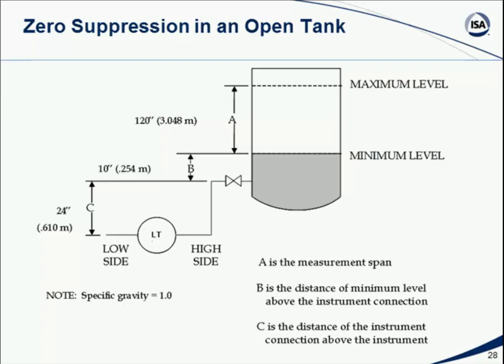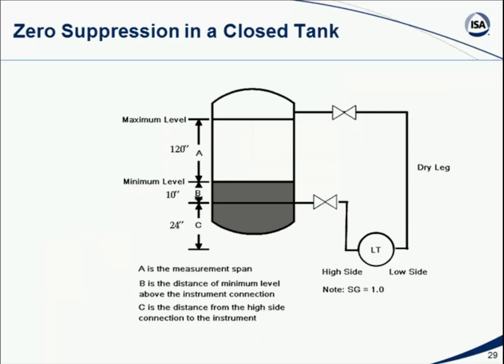Now when I measure 24 plus 10 plus 120 inches, in other words, we're up at the maximum level in the tank, that pressure is what I want to be indicated as 100% in my tank. So my level transmitter is going to be zeroed out to show 0% usable tank when I am measuring a tank level pressure that's equal to 34 inches of fluid. And it's going to show an indication of 100% of the usable value of the tank when I'm measuring 120 plus 10 plus 24 inches of fluid in the tank. Okay, that much pressure. So that's what we mean when we talk about zero suppression in the tank, and also how we have to think about calibrating the pressure transmitter to give us accurate measurement. Okay, so we don't want to think there's something in the tank where there isn't.